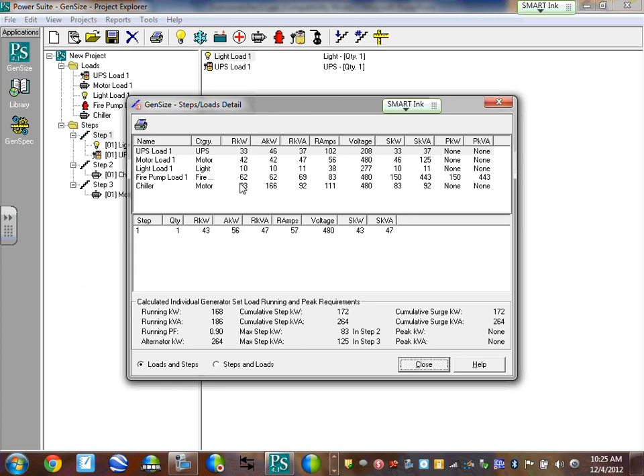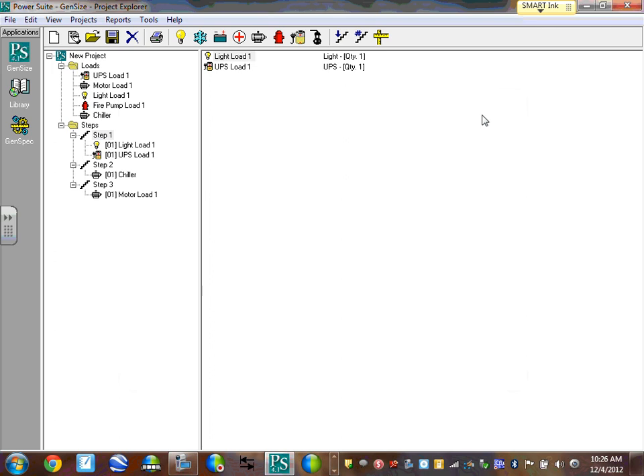Okay, I want to see the running KW. Okay, the chiller actually is what's driving the size here. We've got running KWs here. It's always good to look at to double check the program. So we've got 70, 80, 140, 220. It's sized pretty much right at the end, the maximum. We've got a total running KW right near our generator size. So we might want to bump that size a little bit. And it picked a 230, so I would say, let's go back to sizing.